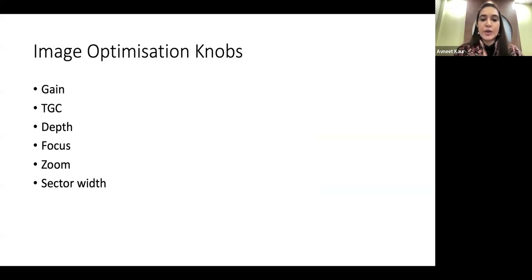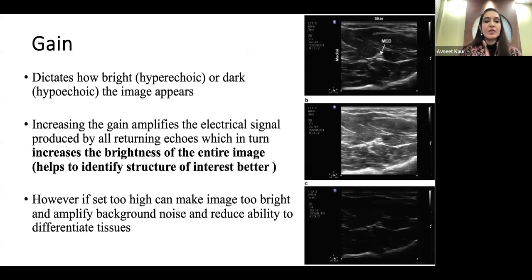Suppose we are doing the B mode or the 2D mode, and now how do we justify that our image is of the right quality? There are six parameters which we talk about for better acquisition of the image, which are gain, time gain compensation, depth, focus, zoom, and the sector width, which I'll be taking one by one. So number one, first we talk about the gain.